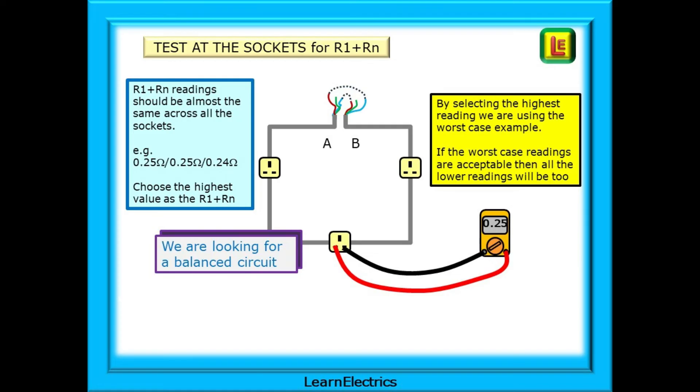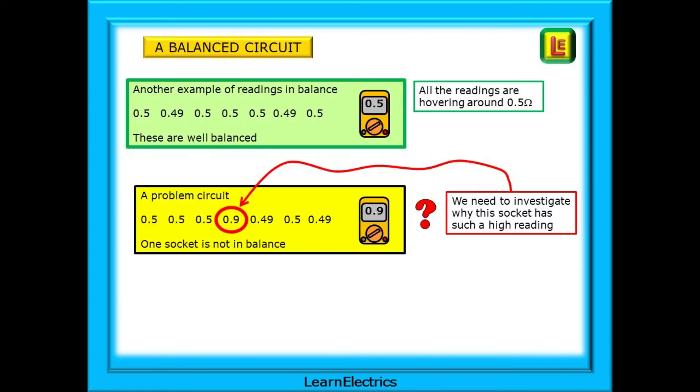We are looking for a balanced circuit. If all the readings are the same, within a very small margin of tolerance, then we can be fairly confident that all is okay with the circuit so far. Another example, and with readings in balance, is shown in the green box. All the readings are hovering around 0.5 ohms. Nothing to worry about here.